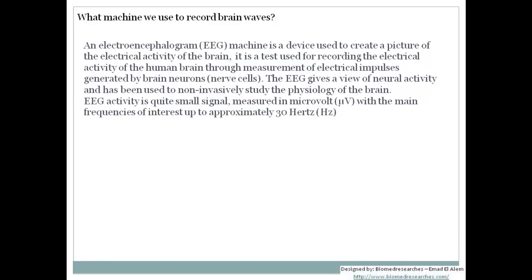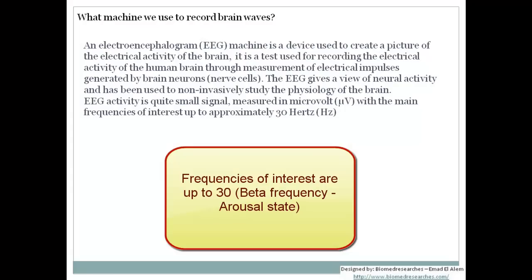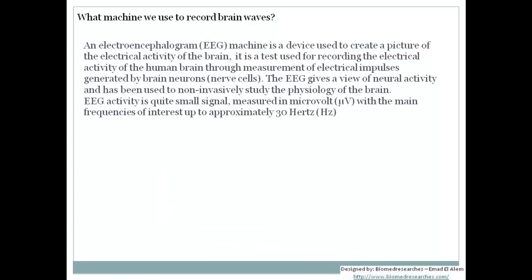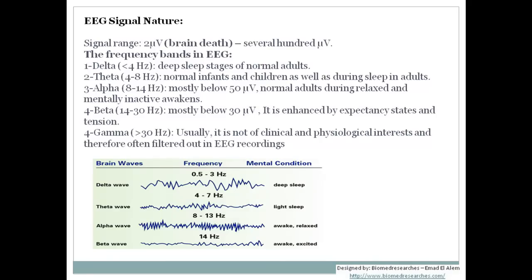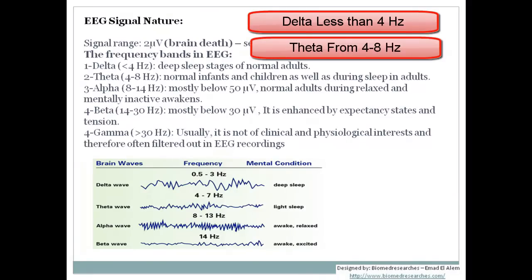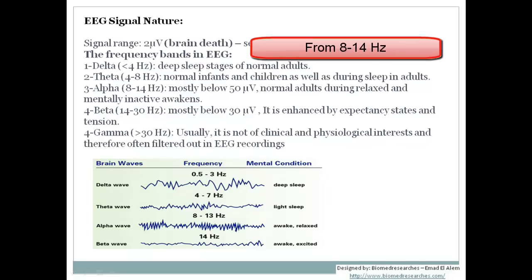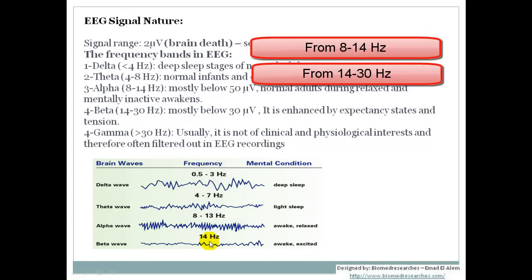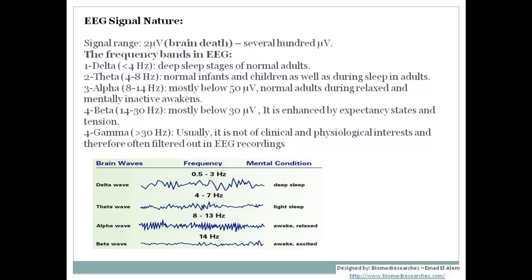The frequencies of interest on an EEG are up to 30 Hz, including up to the beta frequencies which indicate the state of arousal. The main EEG bands are: delta (less than 4 Hz), theta (4–8 Hz), alpha (8–14 Hz), and beta (14–30 Hz). Gamma waves above 30 Hz are not of clinical or physiological interest and are often filtered out. The signal range spans from 2 microvolts, indicating brain death, to several hundreds of microvolts.